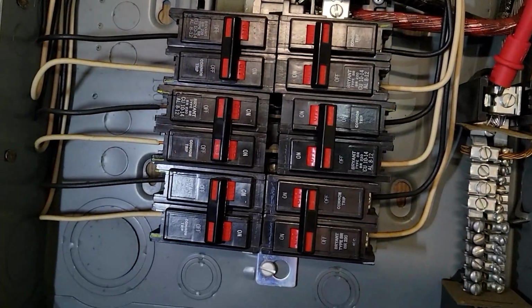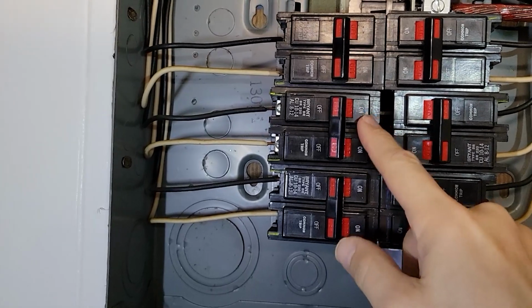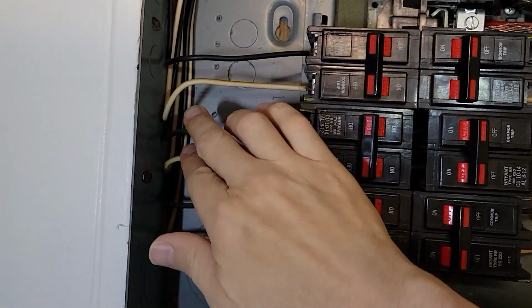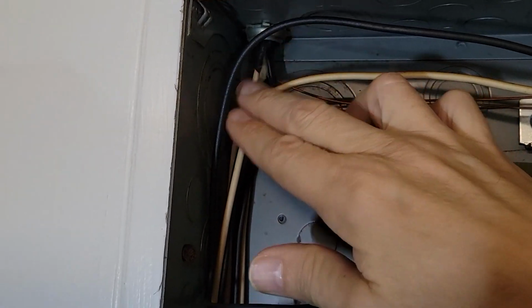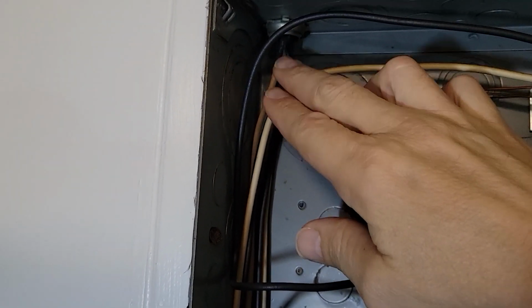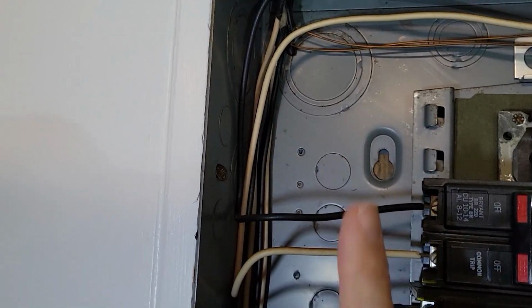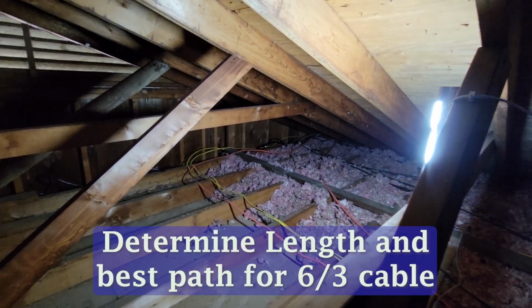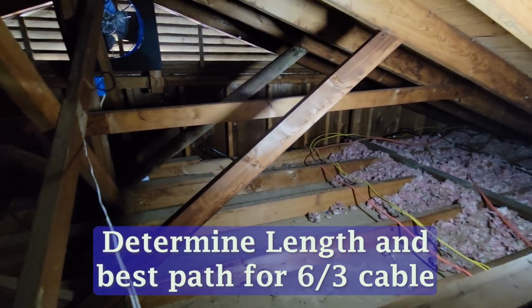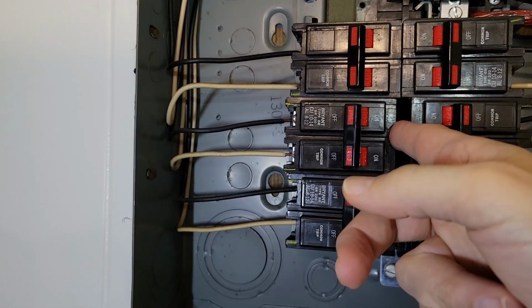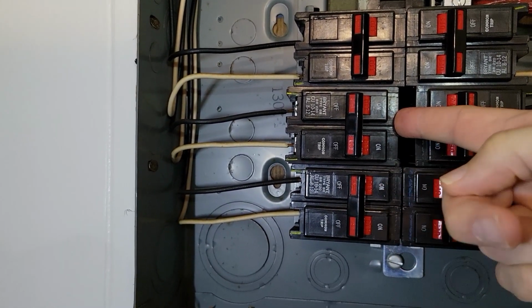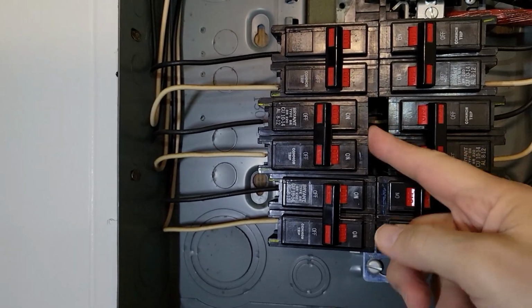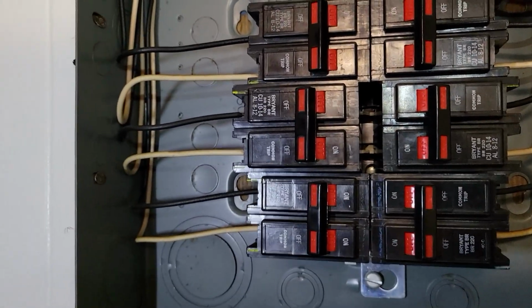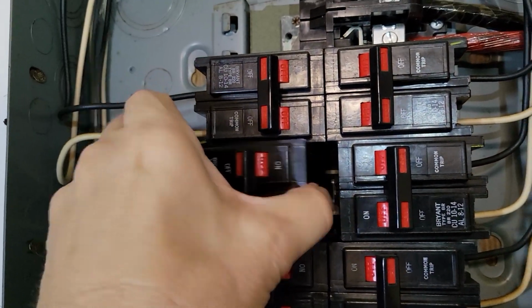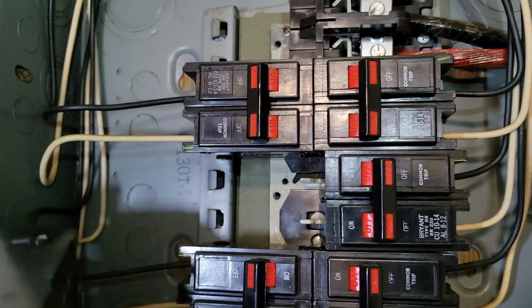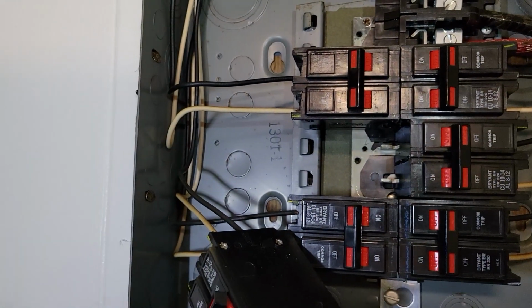For my particular situation, I've decided to replace this circuit breaker here because it comes in on this side. There are two wires that are coming down. By removing those two wires, I should be able to just send a 6/3 up quite easily and make it up into the attic. To remove these, you're going to need some kind of a pry to get in here and push. I used a screwdriver to break it loose. It's very loose right now because it's not fully seated, but you're going to push it out this way and then lift out. And again, there's no current running through this system.